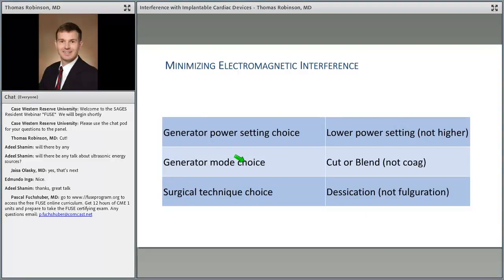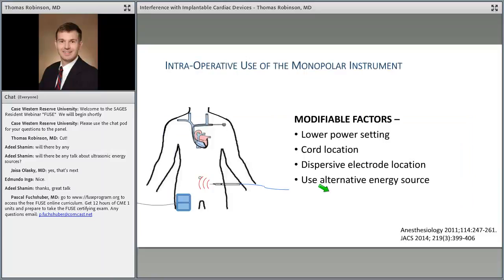All right, so what other things can we do? We can minimize the power setting on the generator. That's the 30 watts coag. You could preferentially use lower voltage outputs, which was mentioned earlier. So that's the cut mode, which has 100% duty cycle, or blend mode, and you should preferentially not use coag if you can help it. And then if you can alter your surgical technique: for say 30 watts power, the generator is going to give off a lower voltage to the active electrode if you're desiccating, which is touching the tissue, versus fulgurating, where you're creating a spark gap and arcing the energy over to the tissue.